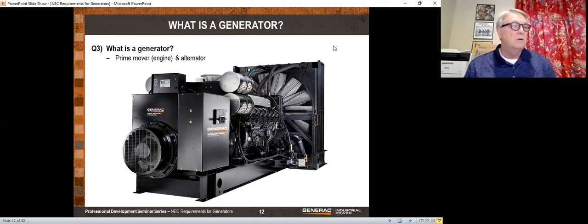I talked to one of our salesmen this morning, and the only conversation I had today, and we're specifying a generator with an oversized alternator. In this case, it's for harmonics. So an oversized alternator may be necessary to control your harmonics, and that's particularly important with variable frequency drives. So you remember, the engine provides kilowatts, the alternator provides volts and amps. So if you need kilowatts, it's got to come out of the engine. If you need volts and amps, it's got to come out of the alternator.